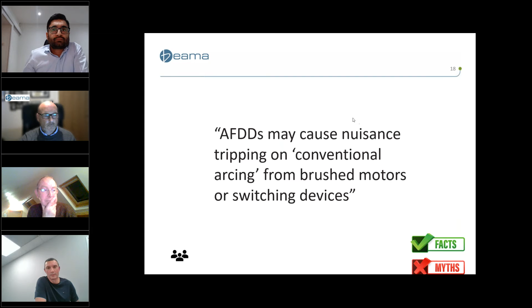Last one before we go to Q&A: AFDDs require a minimum load to function correctly. That's true - all circuit protection devices have a predetermined operating threshold, like a fuse rating, MCB rating, or RCD tripping current. AFDDs need a minimum load current of 2.5 amps flowing in a circuit. Below that, it's not deemed enough energy can be created to cause an arcing fault that leads to ignition.